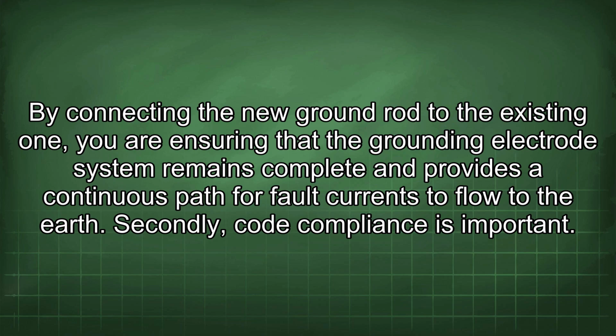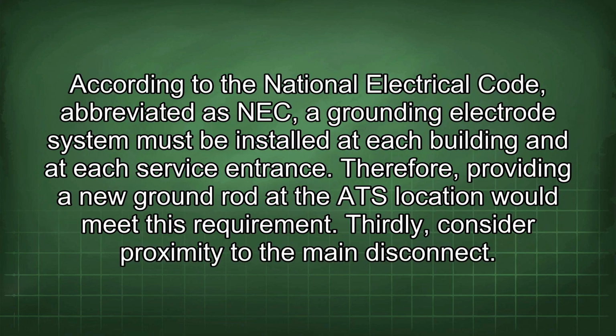Secondly, code compliance is important. According to the National Electrical Code, abbreviated as NEC, a grounding electrode system must be installed at each building and at each service entrance. Therefore, providing a new ground rod at the ATS location would meet this requirement.